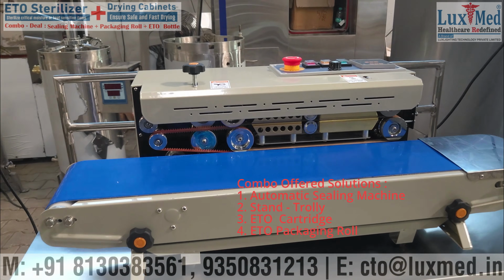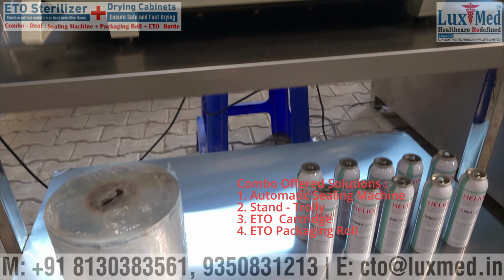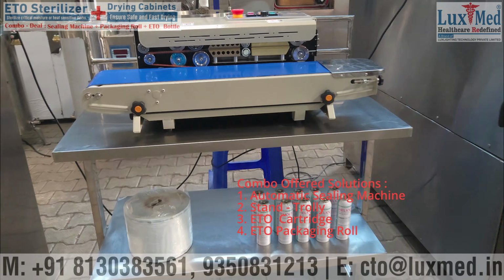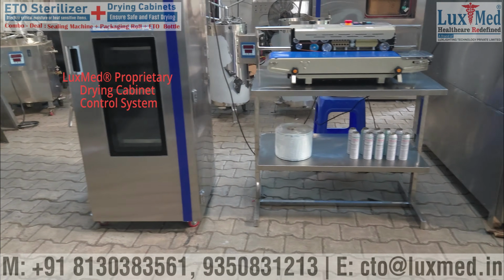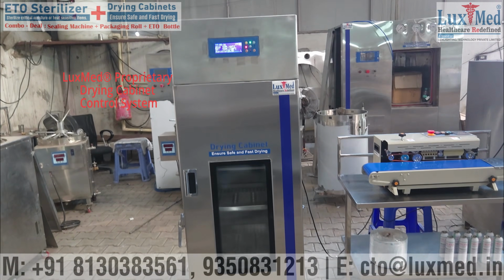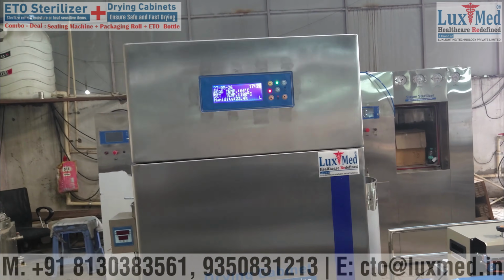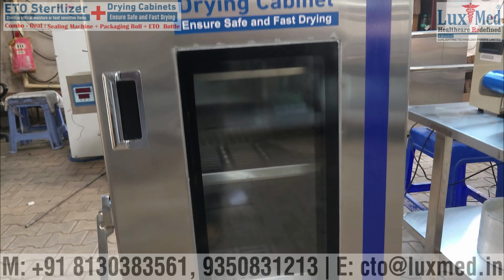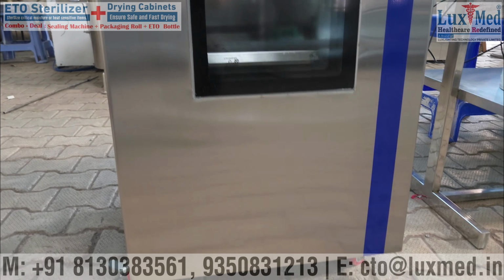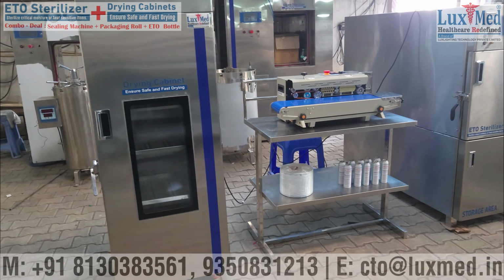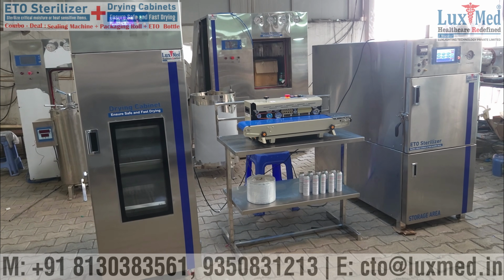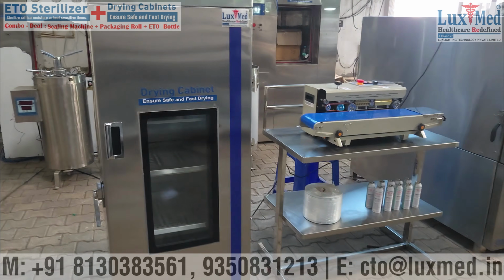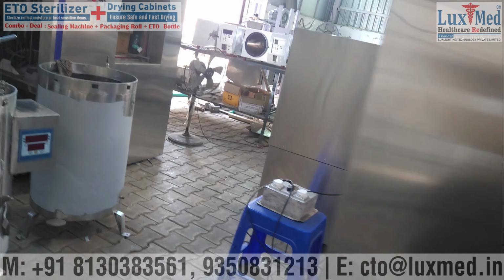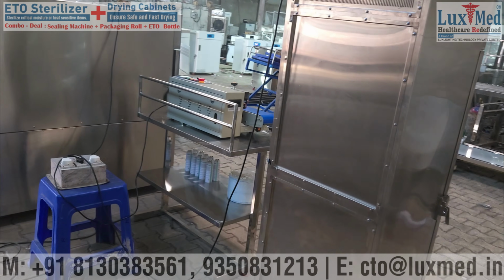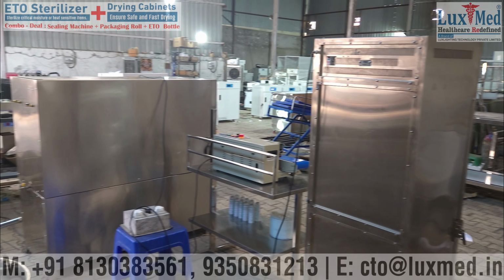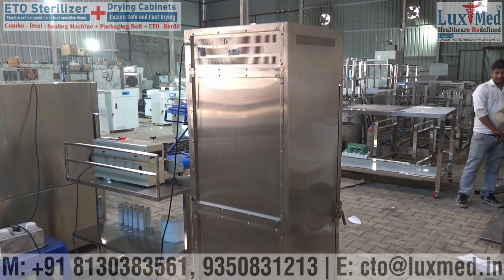ETO sterilizer, ethylene oxide. ETO sterilizers use ethylene oxide gas to sterilize medical and surgical devices that cannot withstand high temperatures or moisture, such as catheters, plastic instruments, and delicate optics. Mechanism: the gas penetrates packaging and disrupts the DNA of bacteria, viruses, and fungi without damaging the material. Cycle: operates under vacuum at low temperatures, typically 30 degrees Celsius to 60 degrees Celsius. Key features: requires automated humidity controls, gas leak detectors, and exhaust systems to safely remove toxic gas residue after sterilization.